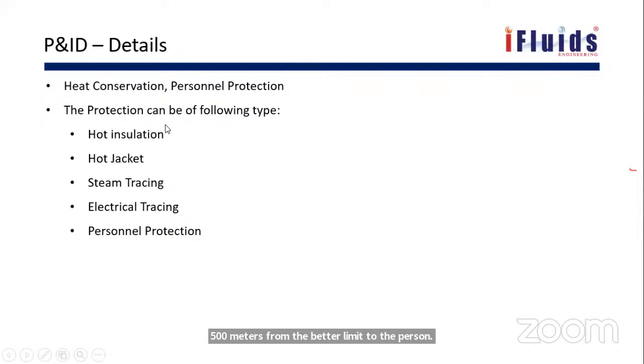So if it travels 500 meters, say for a 10 inch line, it has some heat surface area, right? Through that surface area, it will lose heat. To avoid that, we need to provide insulation, otherwise the temperature will drop. Say the temperature needs to be maintained at 150, and with no insulation it will drop to a lower value, but at my destination I need 150. So we need to provide heat conservation type insulation, with a thermal conductivity such that it will not allow the heat to transfer.